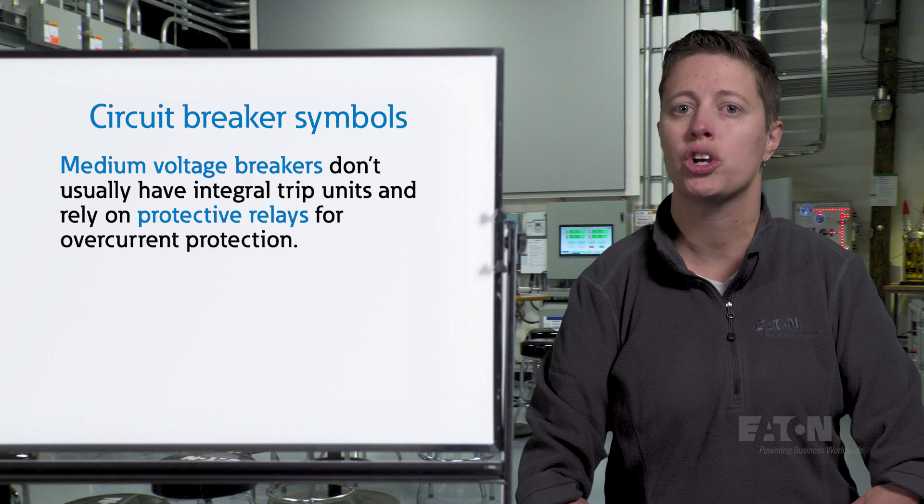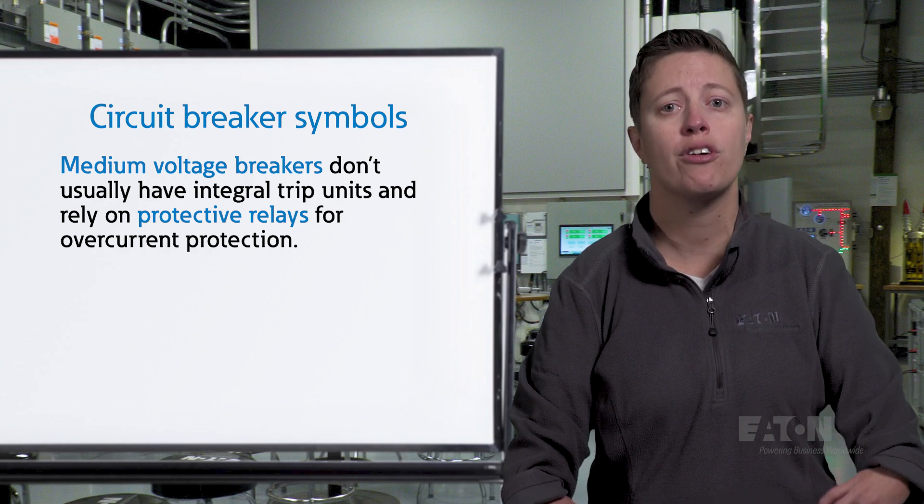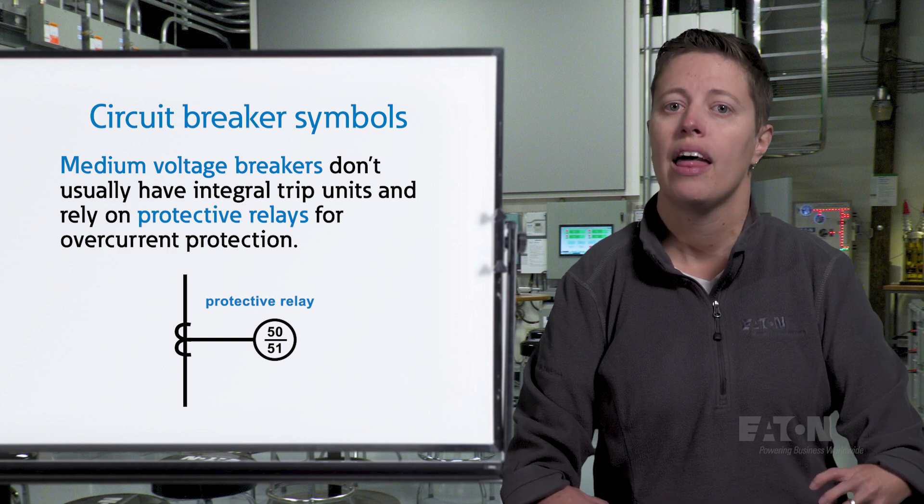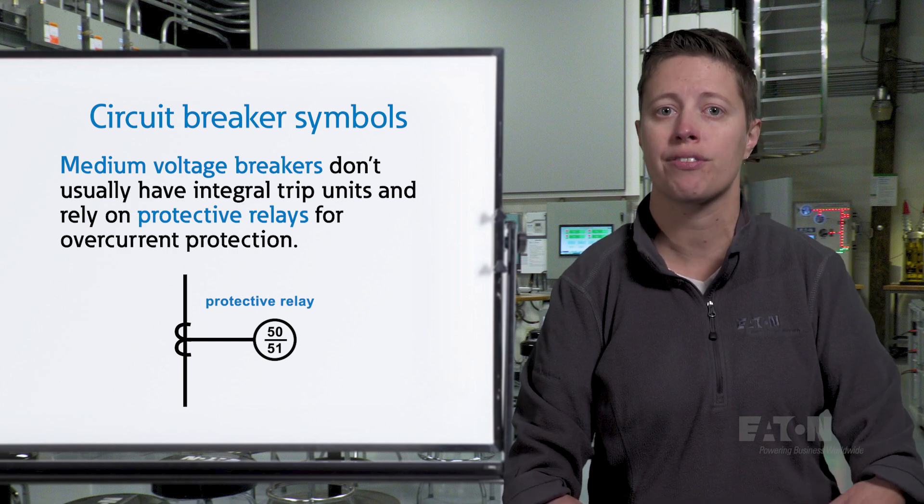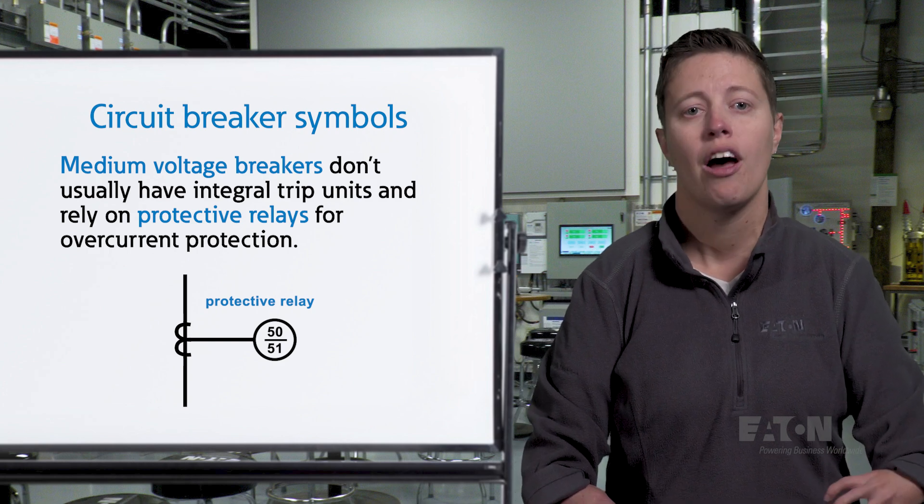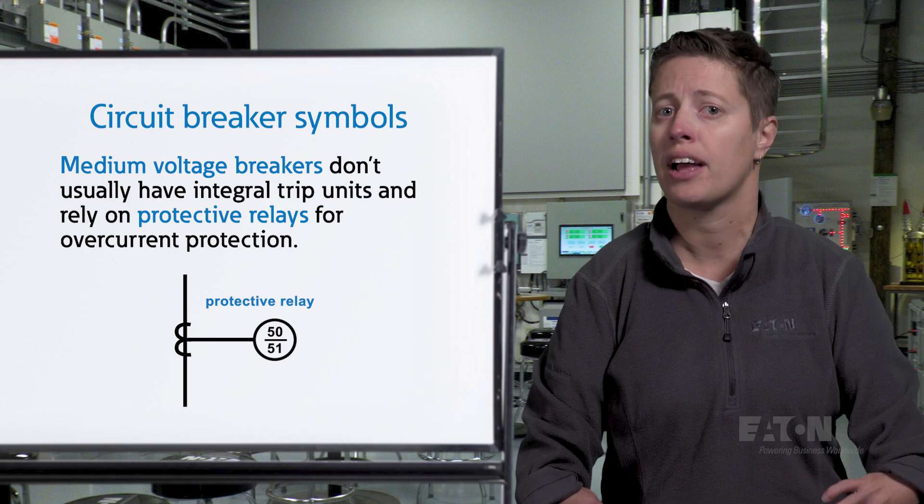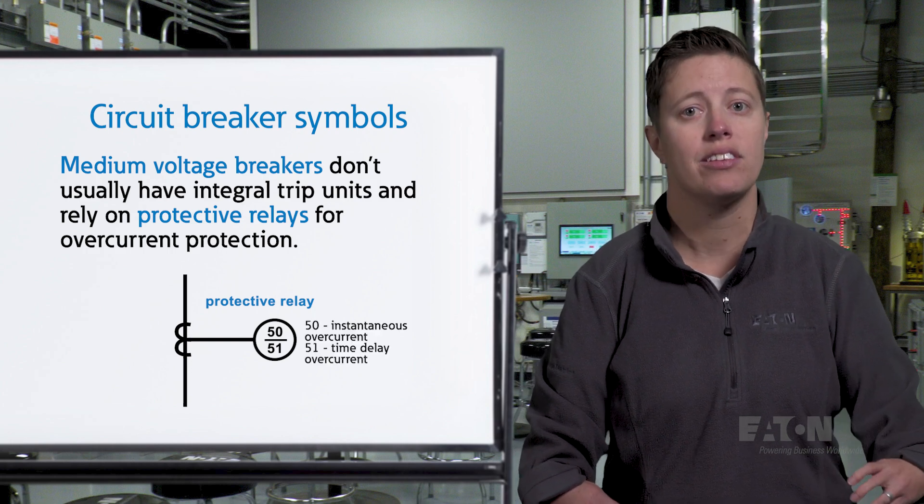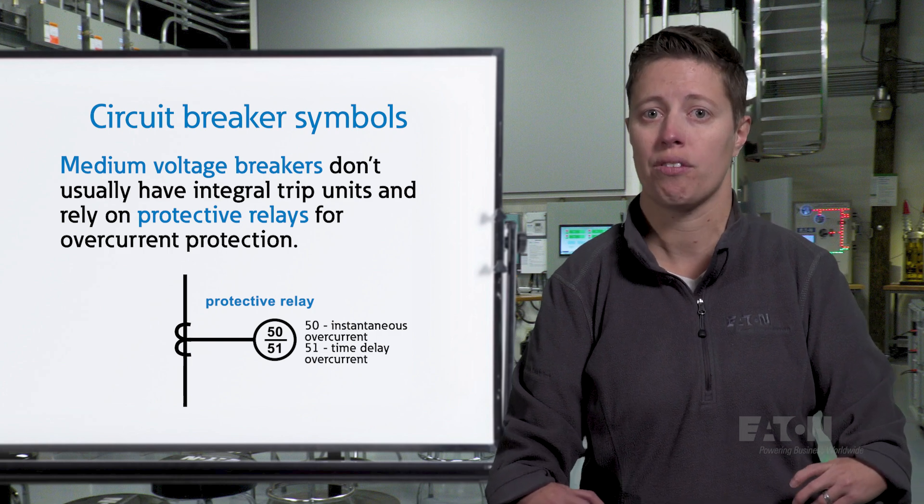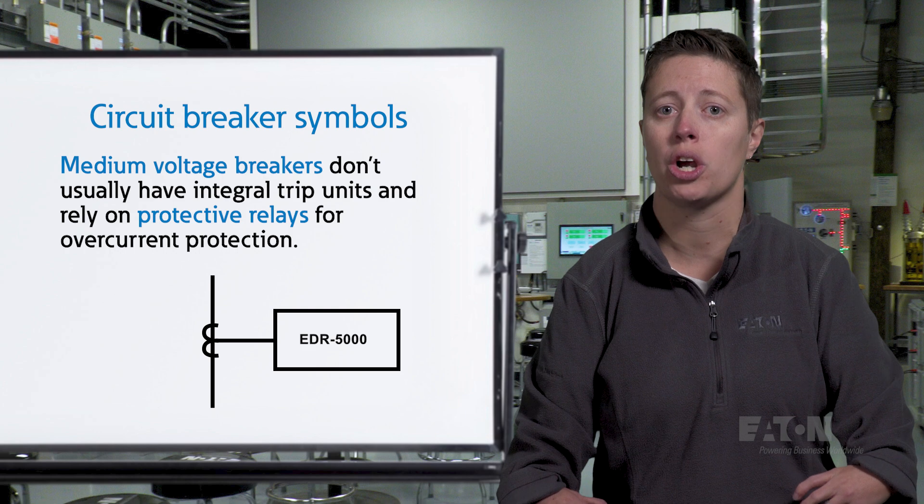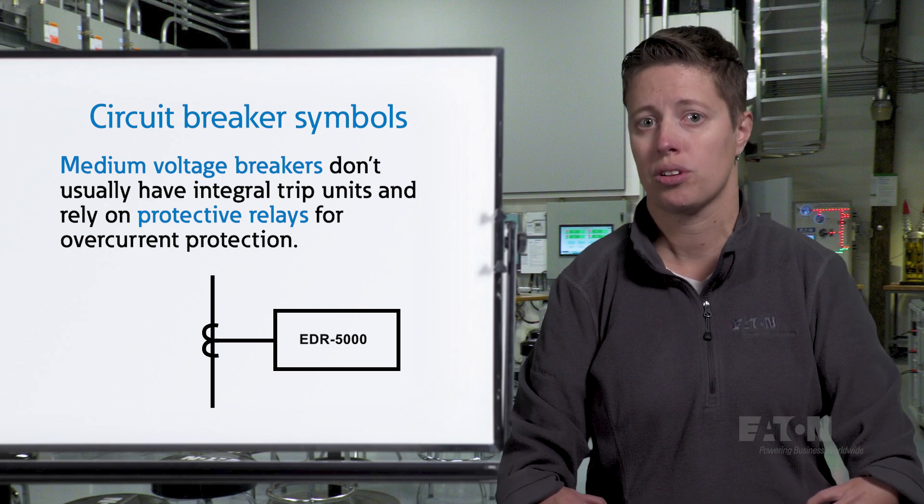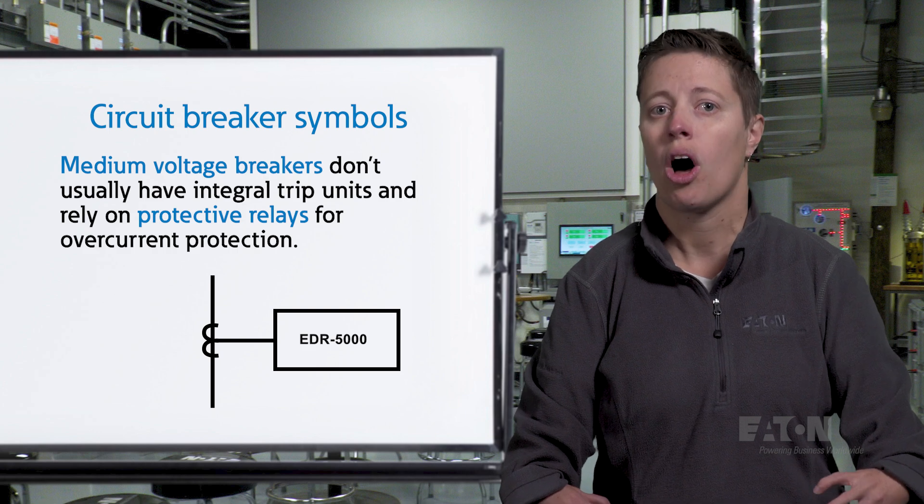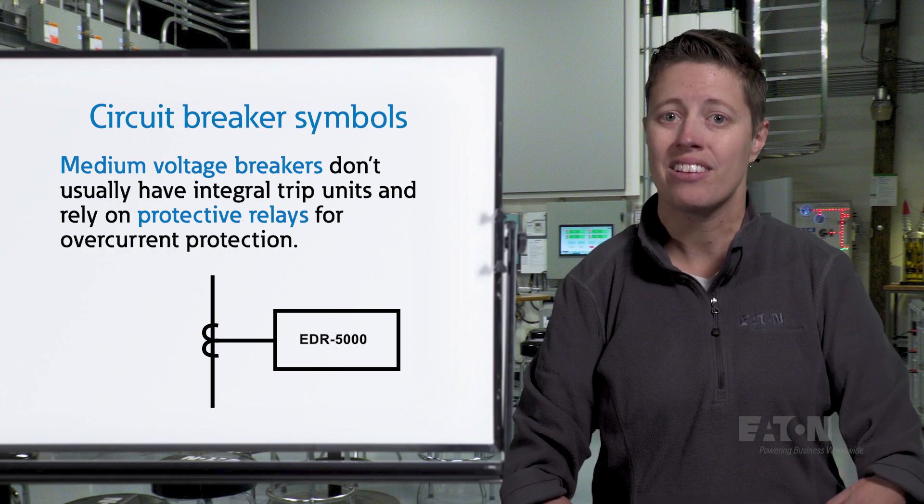Medium voltage breakers do not usually have integral trip units and rely on protective relays for overcurrent protection. A protective relay may be indicated by a two-digit number within a circle. This two-digit number is a reference to the ANSI device number corresponding to the function the relay performs. For example, a circle noting 50-51 indicates the breaker is protected by a protective relay performing function 50, instantaneous overcurrent, and function 51, time delay overcurrent. The protective relay may also be shown by a rectangle with the model number of the relay to be used. This example shows an Eaton EDR5000 protective relay. For more detail on protective relays, see our video on the basics of protective relaying.